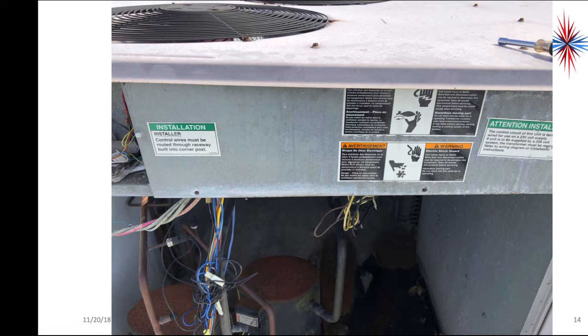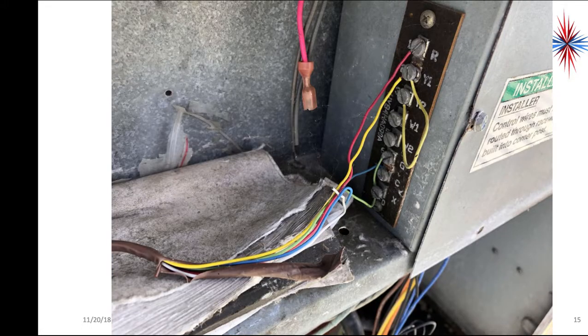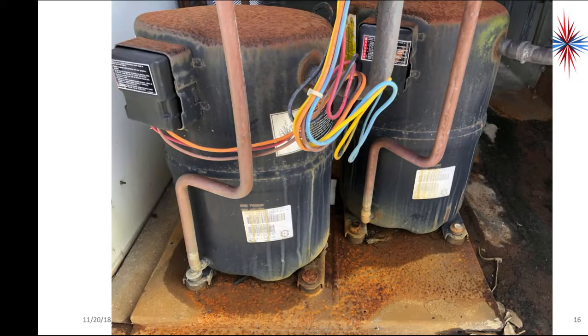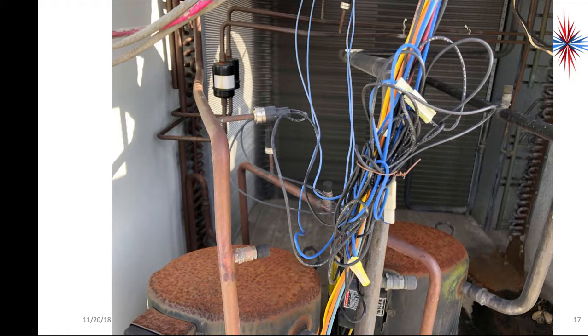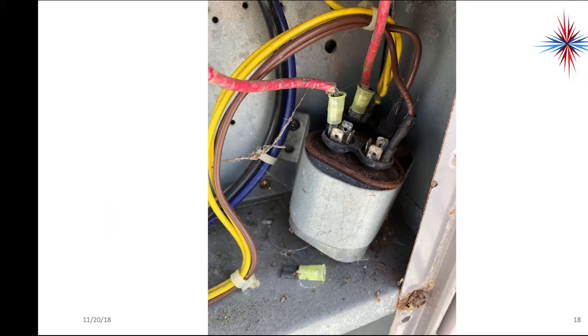Okay, wiring cover's on. Pull the wiring cover. Well, look at the side of it first. You'll note that Y1 and Y2 are jumped out. Again, this is important. Okay, come down here, take a closer look at the compressors just to make sure the wiring matches. We get the model and serial numbers off the compressors. Again, there's my great big old ball of control wire. Again, this is going to be important as we continue our conversation.